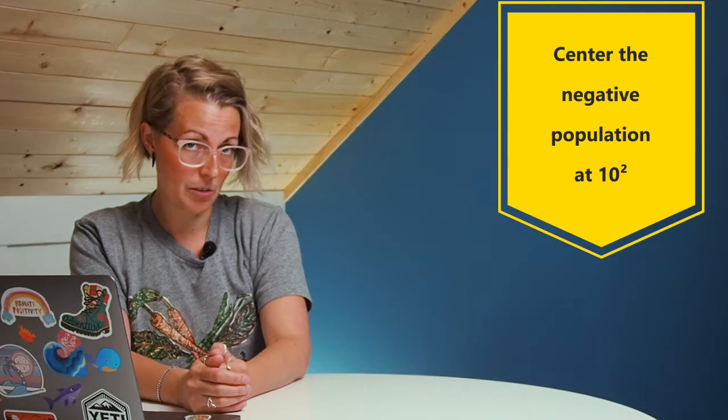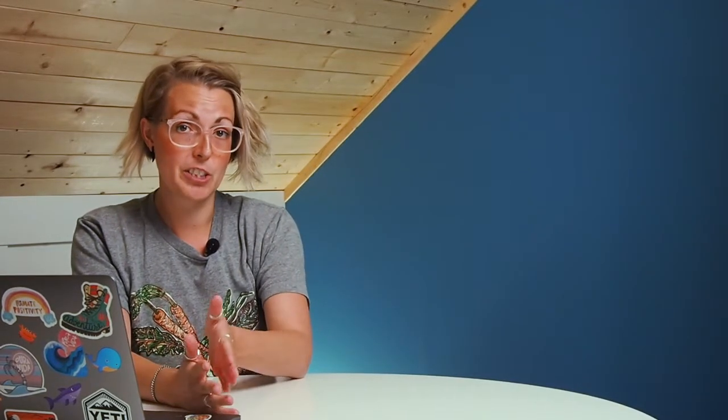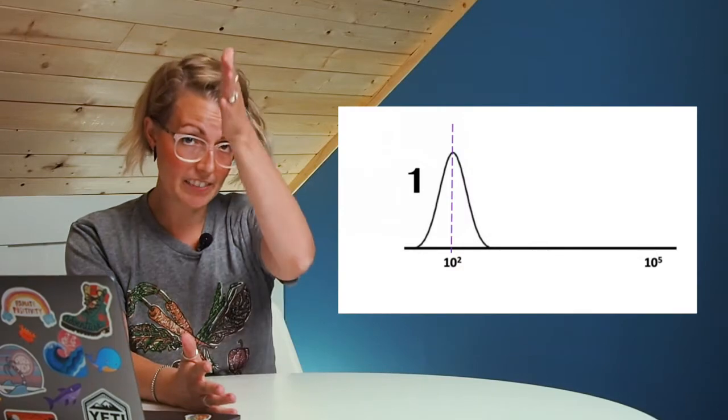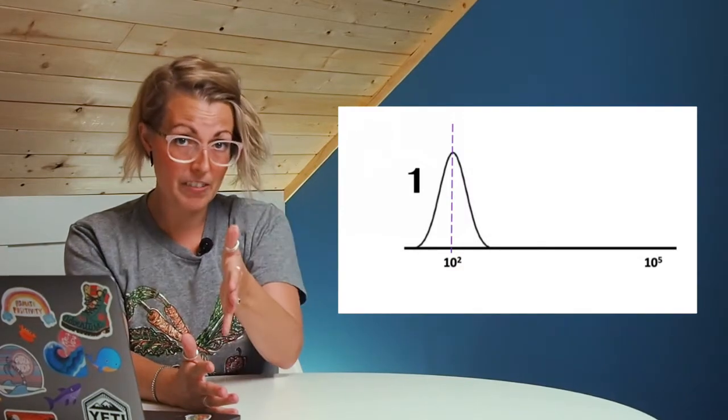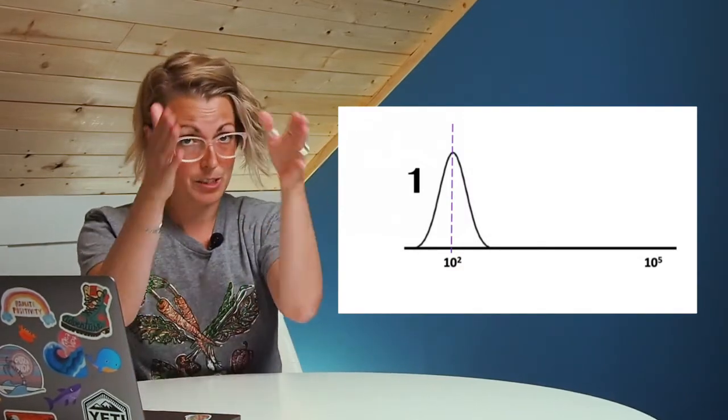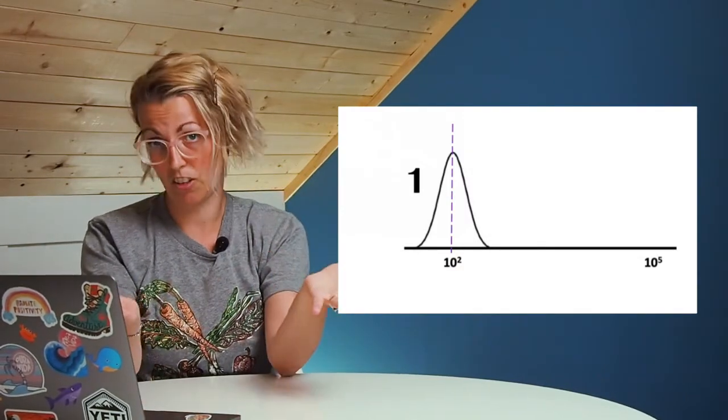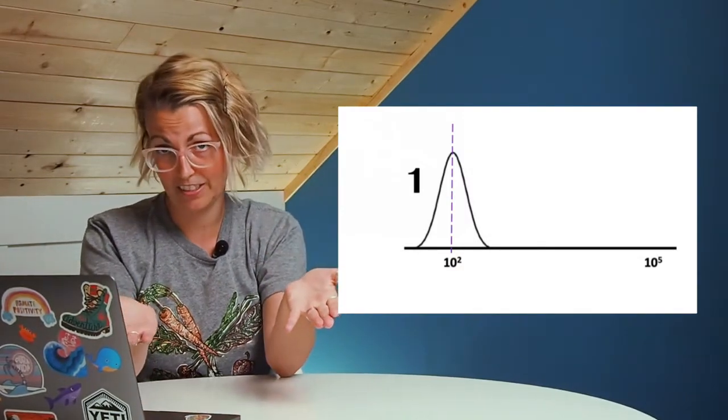On new digital cytometers, there are two really easy basic things you can do to get pretty good voltage settings. First, set your negative population so that it's centered nicely around 10 to the 2, or around a hundred. Essentially, you want the median of that population to be right above a hundred so that the spread is on either side. This will generally give you a background that's outside of the noise.